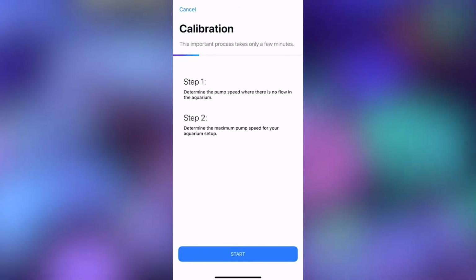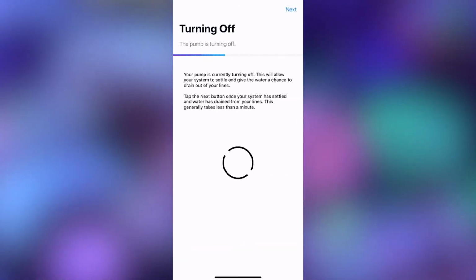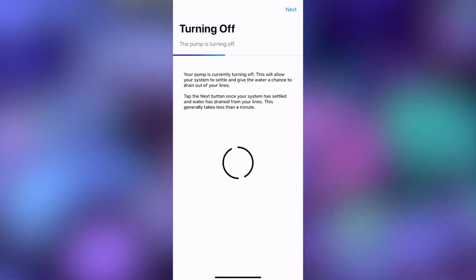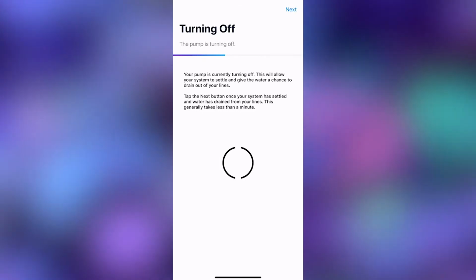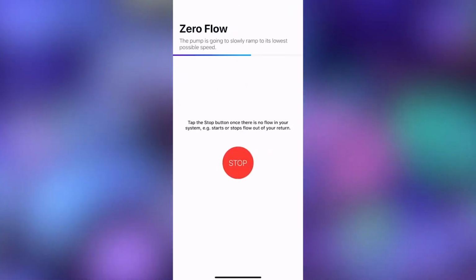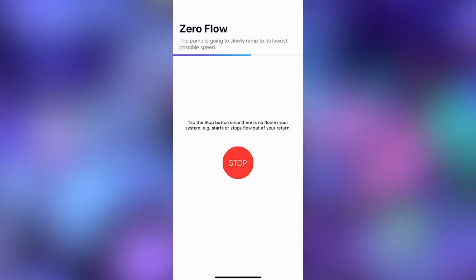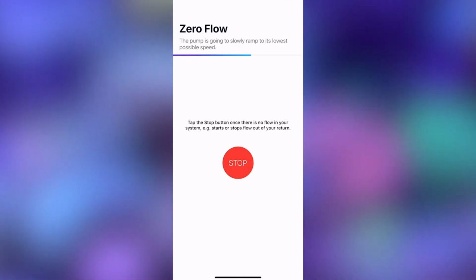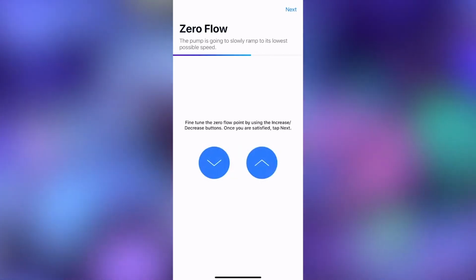After this, we are going to run the calibration. If this is the first time you're installing the pump, it is going to prompt you to do this. You can skip it, but if you click on calibrate, then what it's going to do is initially turn off the pump and then walk you through the calibration process. The purpose of calibrating is so that you can create a neutral water level for things like feed mode. And also, if you turn the pump down to 0, it will actually continue to run at that level where you have neutral head pressure.